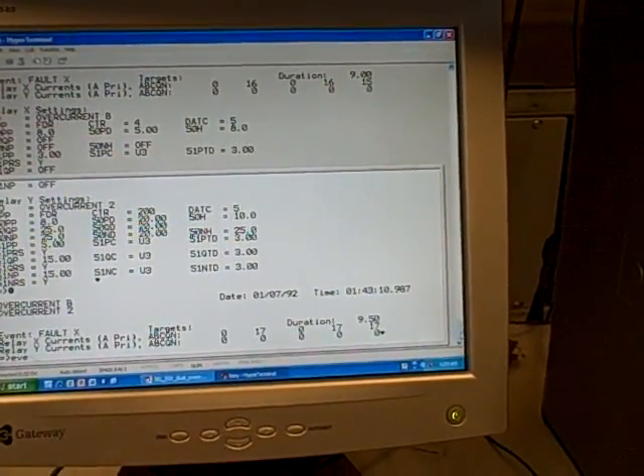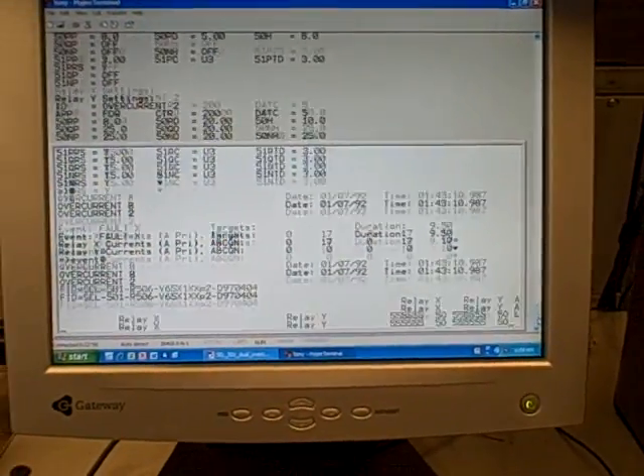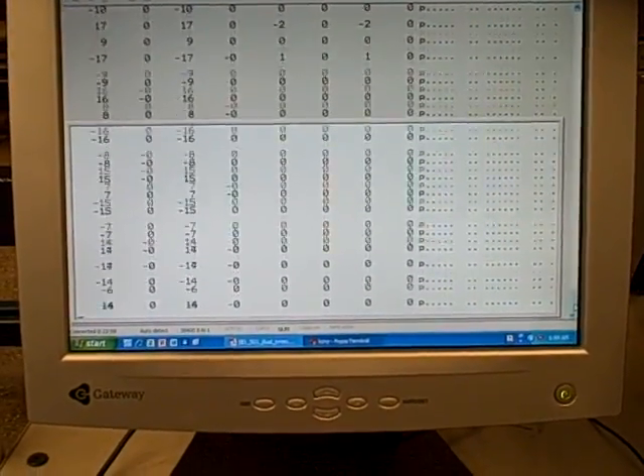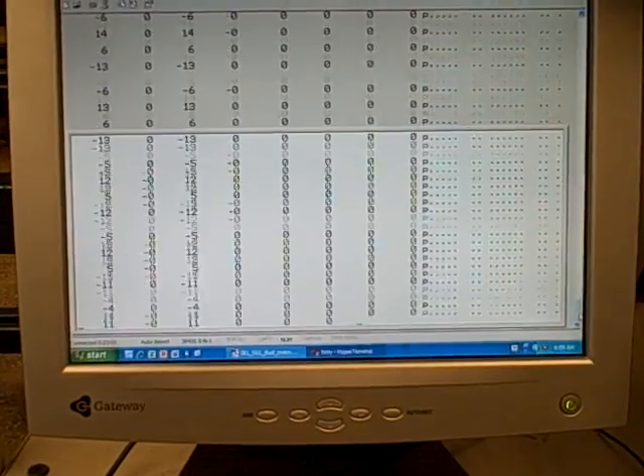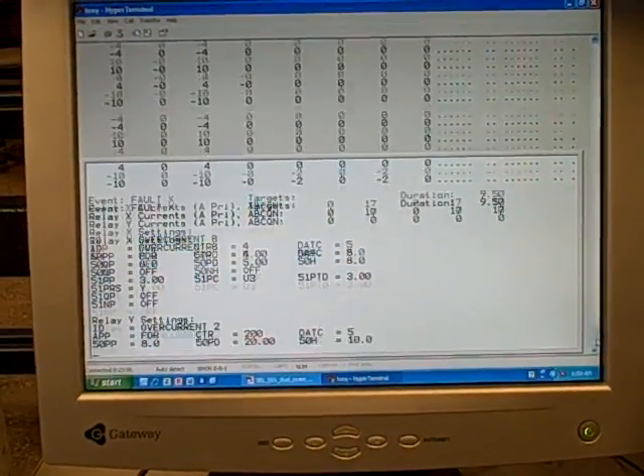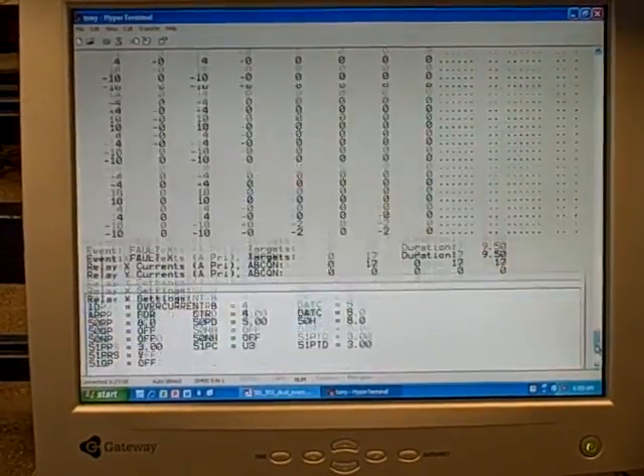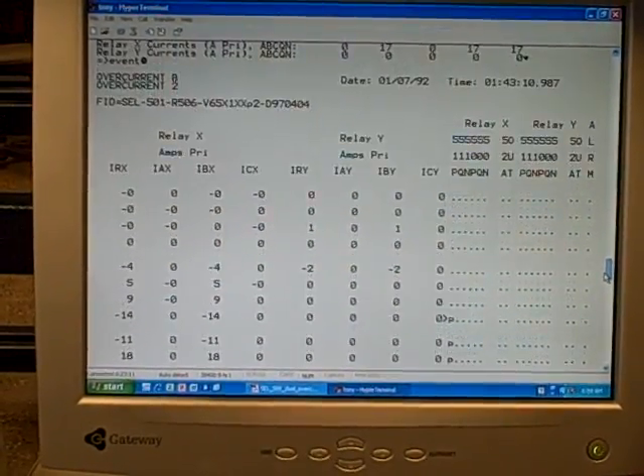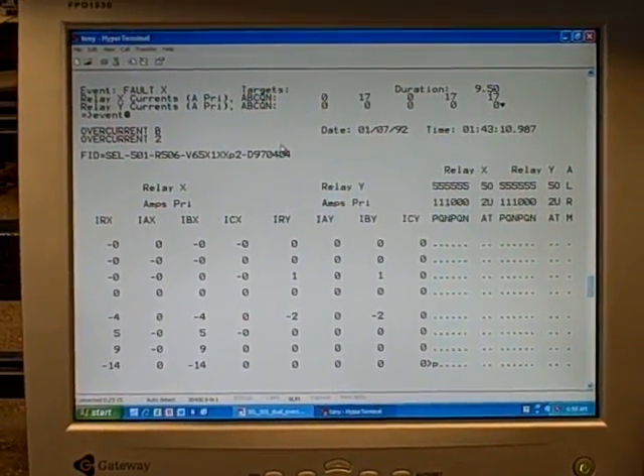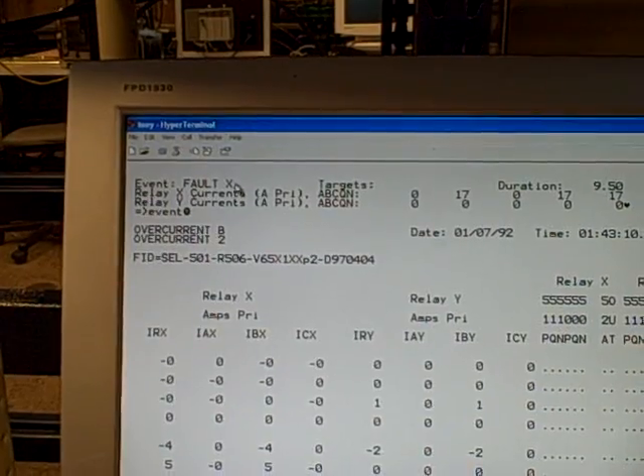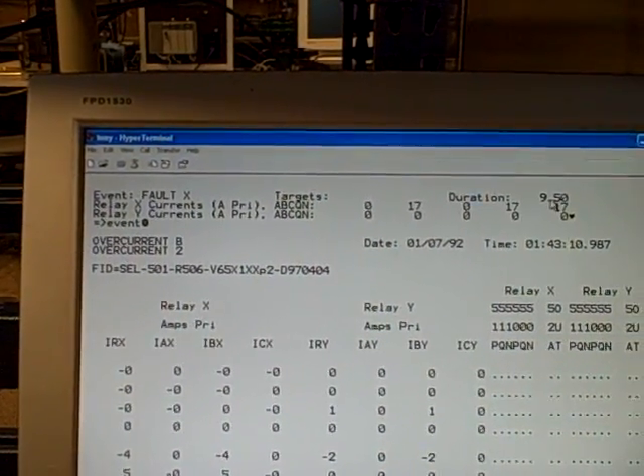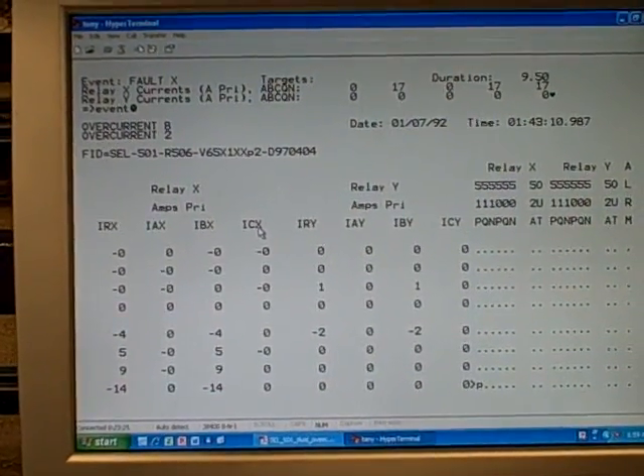If we come over to our serial terminal screen, I can type in the word event and digitally communicate with the relay. When I do that, it gives me a report of the event, what it detected that would be considered noteworthy or worthy of being called an event. If I scroll up and examine what happened, we see it picked up a fault on relay X for duration 9.5 cycles.